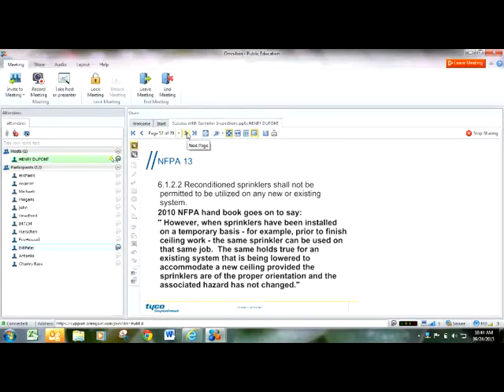Common problems affecting sprinkler systems. Reconditioned sprinkler heads. We talked a little bit about how sprinkler heads don't go off for any reason whatsoever. This is the 2010 edition of NFPA 13, and it's kind of vague when it says reconditioned sprinkler parts. Well, I read that and interpret it as: if you take a sprinkler head out because you're moving walls, doing renovations, whatever, you don't put that sprinkler head back in.